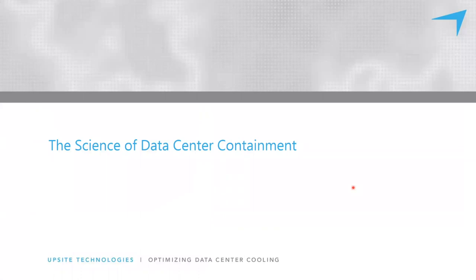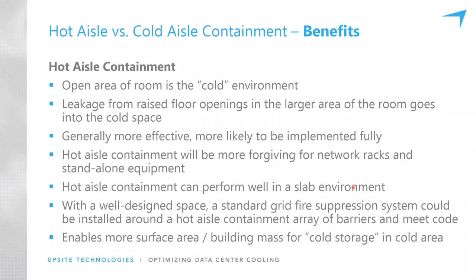So let's now get into some of the science behind these processes. One of the common questions I get is, what's better, hot or cold aisle containment? Studies, both theoretical and real world studies, have shown that hot and cold aisle containment are equally effective if implemented fully. And that's a big if. If implemented fully, they're equally efficient, and they're really the same thing. All we're doing is creating a defined flow path for the cold air and a defined flow path for the exhaust hot air back to the cooling units. Where you separate it is what you call it. If you're separating it at the cold aisle level, it's cold aisle containment. If you're separating it near the hot aisle on the return path, then it's hot aisle containment.